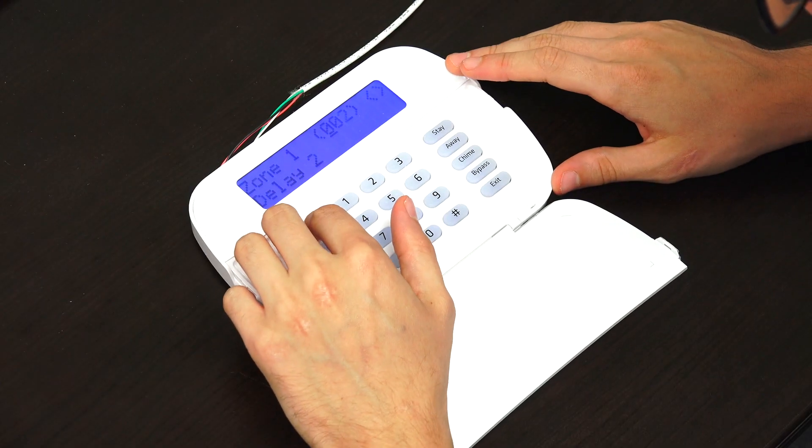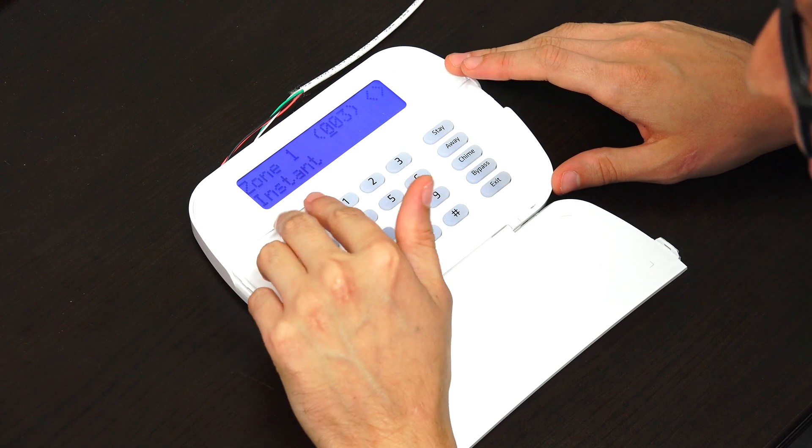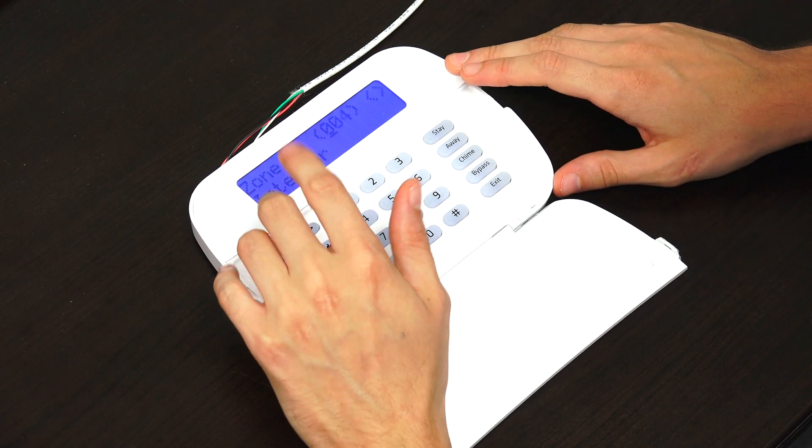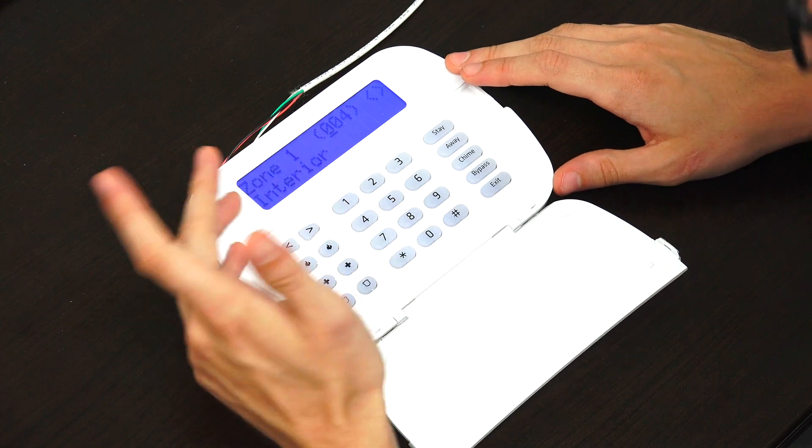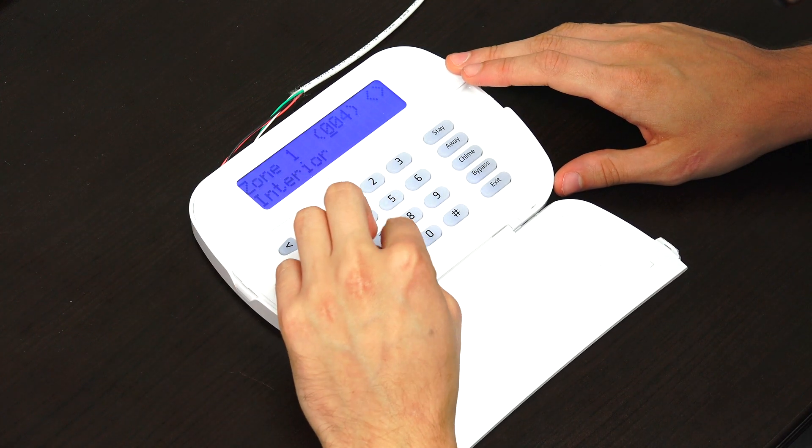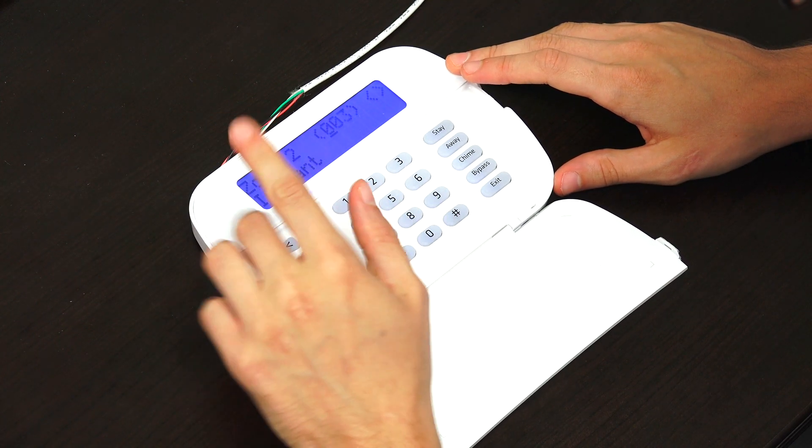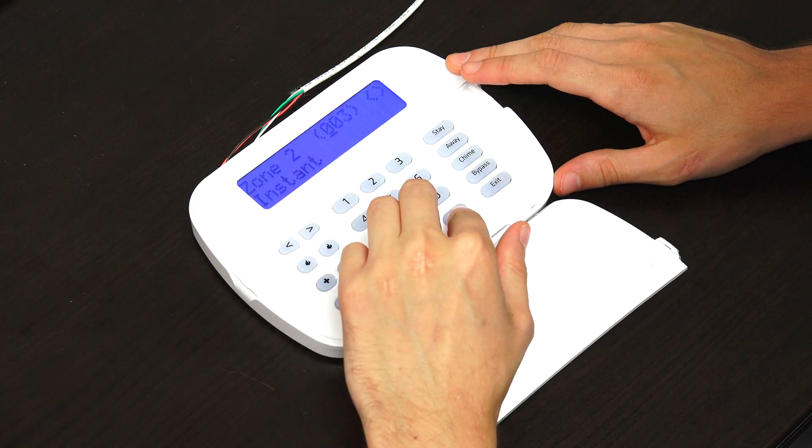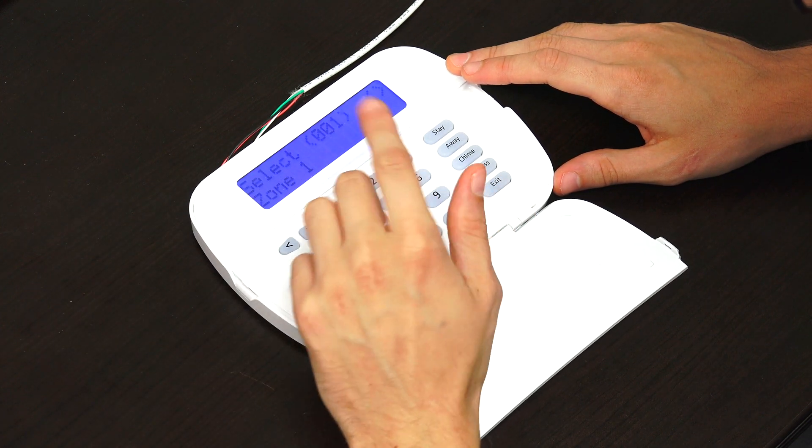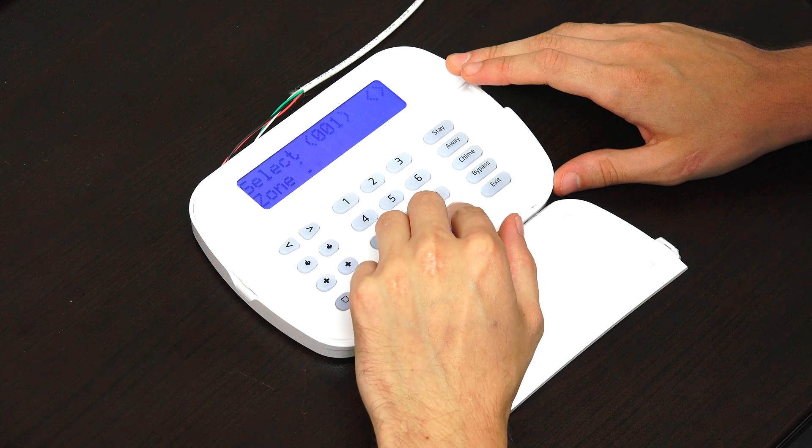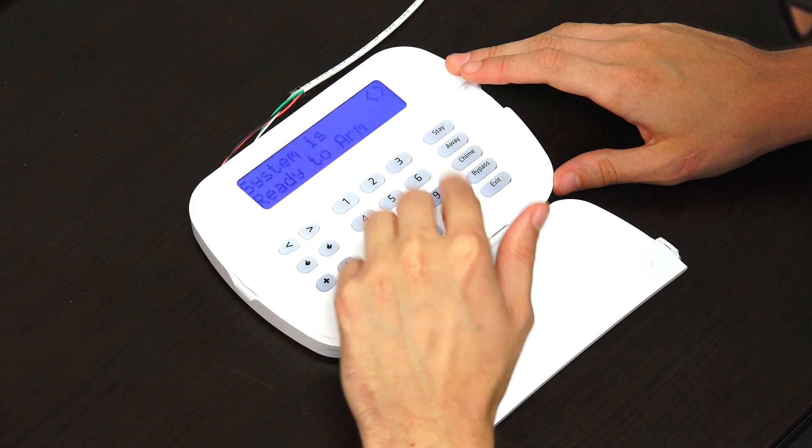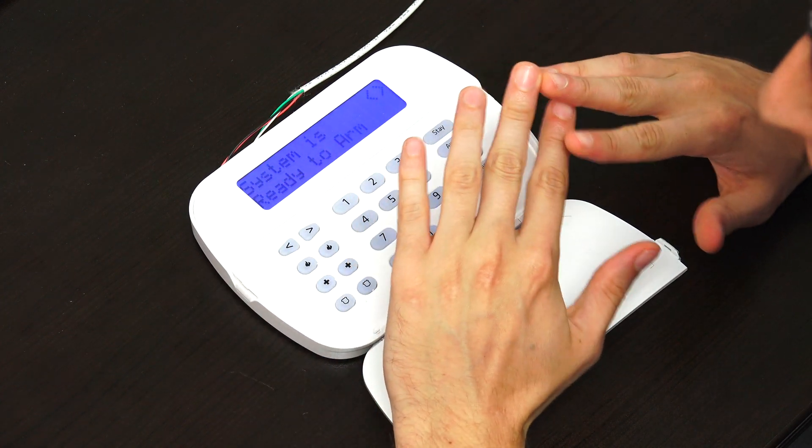And then it's going to ask us for the three-digit zone definition. Now, you should look in the manual for your Neo system to see the complete list of zone definitions. But if you scroll through them, you can see a couple of delay options, like entry exit delays, instant, interior. So we'll go with interior. And we'll press star to confirm it. And then it's going to take us to the next zone. But we don't need to set up a second zone right now. So we'll just press the pound key to go back. So that's how you would assign a zone definition.